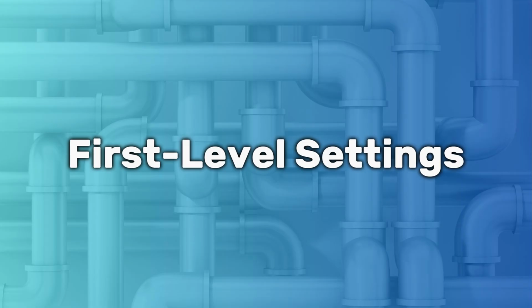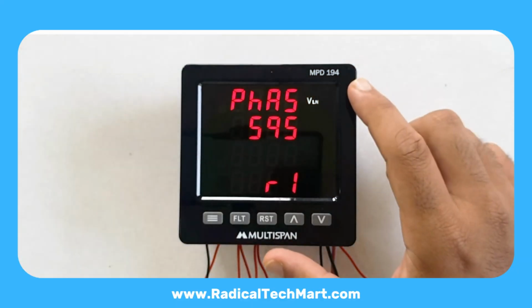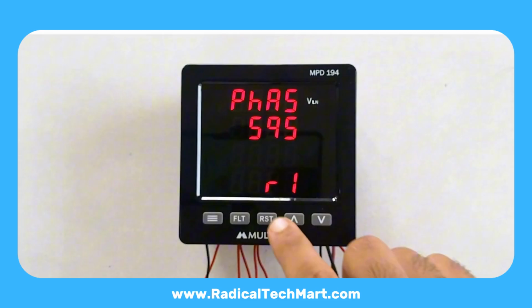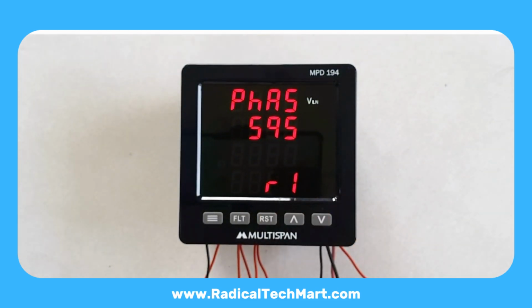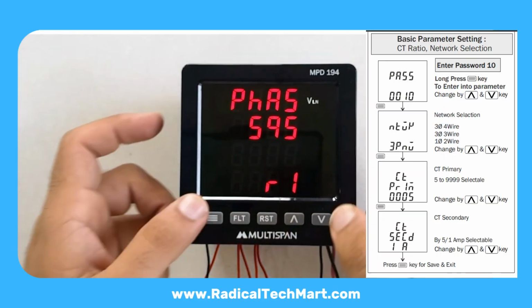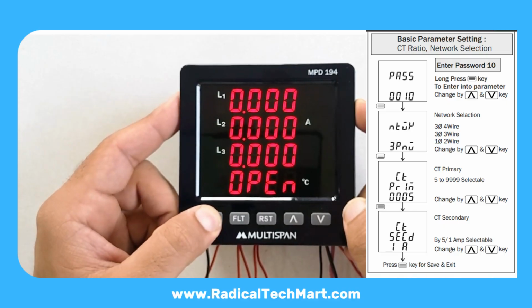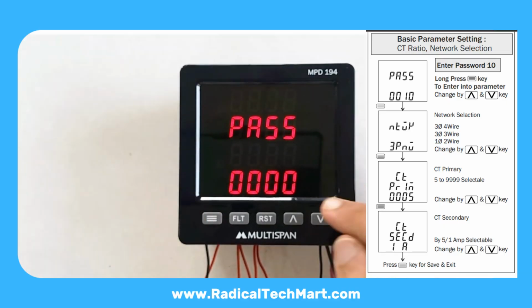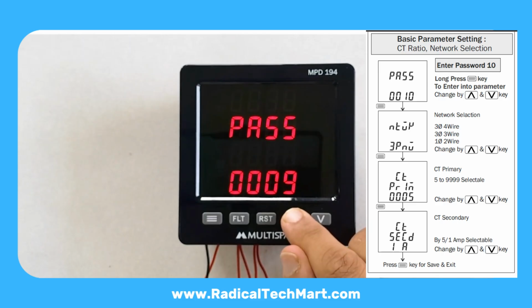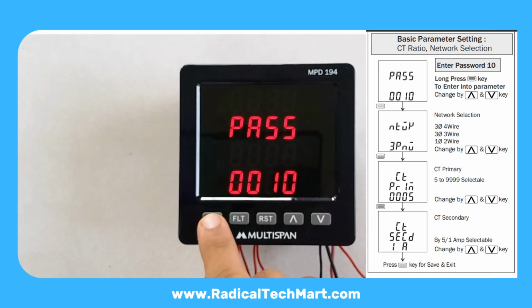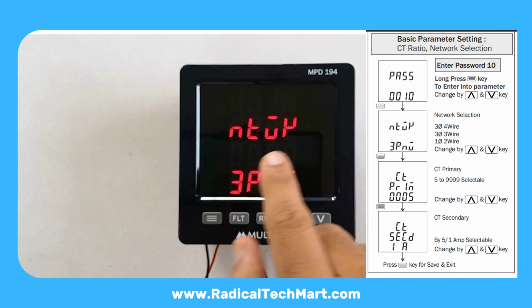First level settings, CT and network. When we power up the meter, the display initially shows a phase sequence error because we have looped only a single phase. To enter basic settings, press set once and release. Press and hold set again until pass appears. Enter password 10 using the up-down keys. Press set to enter.